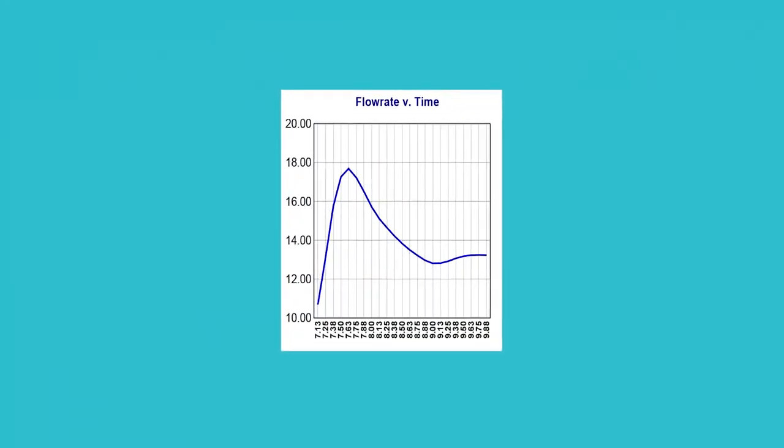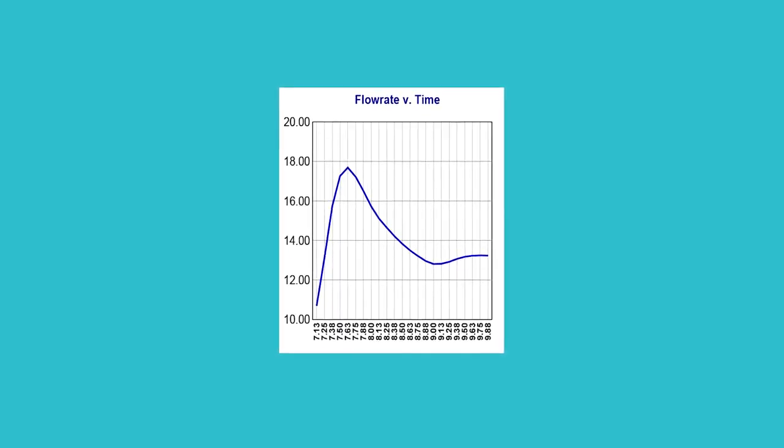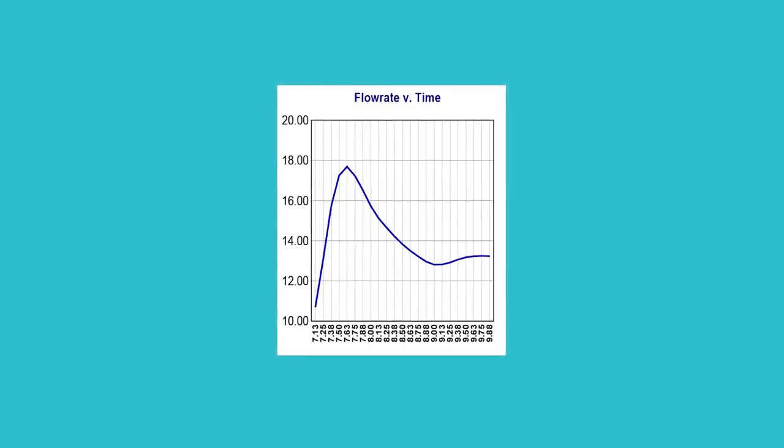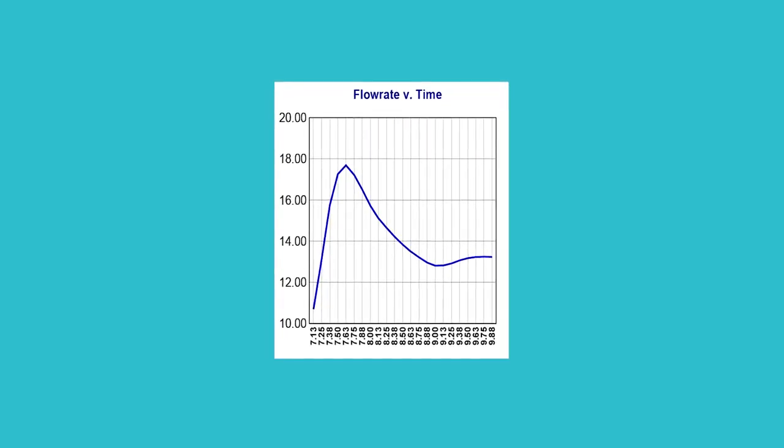You can see the gas flow trend is not steady. If you see this result, look for and eliminate a source of temperature change before running a retest.